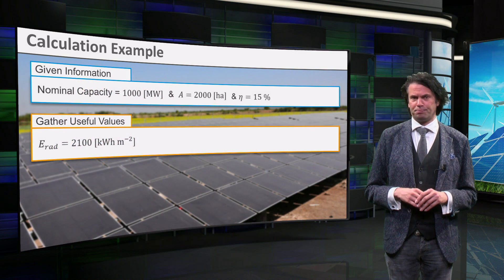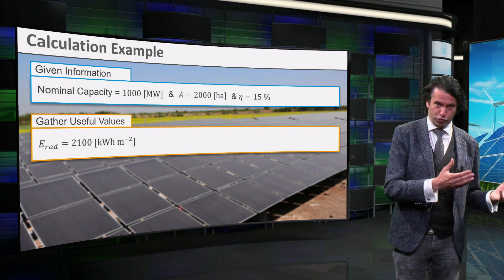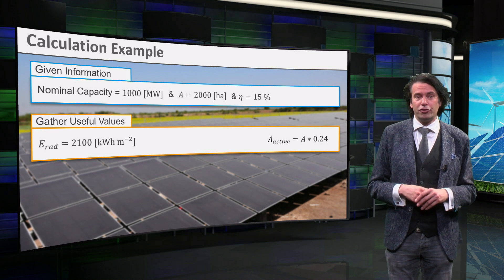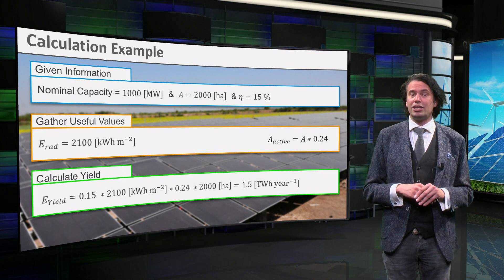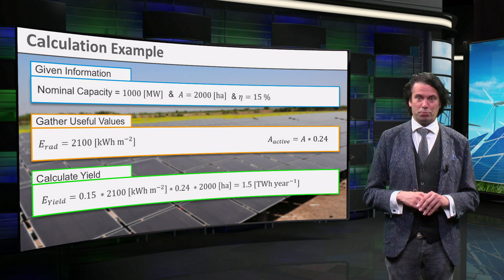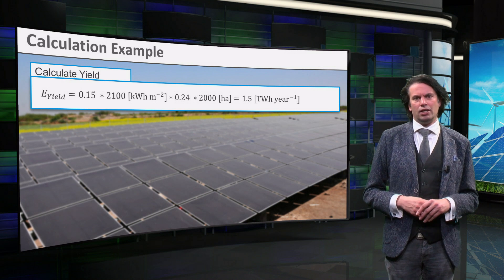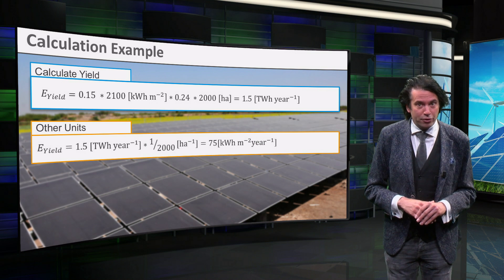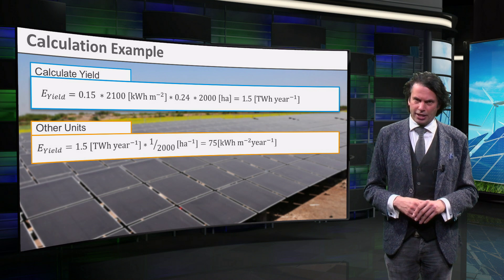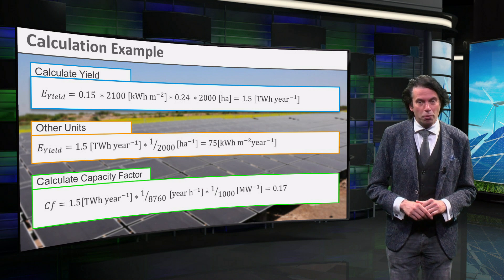We know the surface area of the farm; however, this should not be confused with the active PV module surface area, which absorbs the light. We will take an active area of 24 percent. Ultimately, the yield is 0.15 times 2100 kWh per square meter per year, times 0.24 times 2000 hectares, which equals 1.5 TWh per year. The energy density is then 1.5 TWh divided by 2000 hectares, equal to 75 kWh per square meter per year. Finally, the capacity factor is calculated by dividing the energy yield by the installed capacity multiplied by the hours in a year, resulting in a value of 0.17.